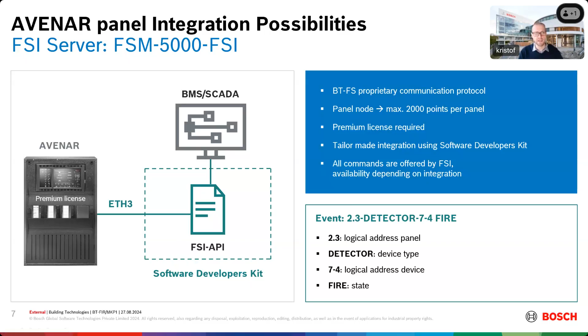This is an example of the string that you receive in your building management system. First of all, it provides you the logical address of the panel. Then it gives you a device type like a detector. Then you get the logical address of this device, and you receive this state. So in this example, it's a fire detector from panel cluster 2, the third panel. And on that panel, it's zone 7, the fourth detector, who gives you a fire alarm. So this is basically what FSI is providing you.